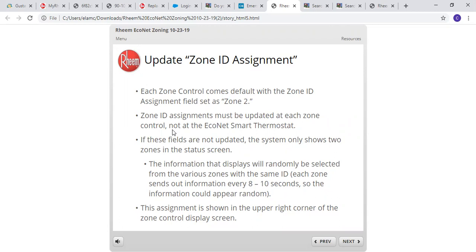So if you go to whatever zone you're going to next, you have to go in there and physically change that and set your zone assignment up in the zone stat. If these fields are not updated, the system only shows 2 zones in the status screen. So they're going to operate as a 2-zone system. The information that displays will randomly be selected from the various zones with the same ID. Each zone sends out information every 8 to 10 seconds, so the information could appear random. This assignment is shown in the upper right-hand corner of the zone control display screen.